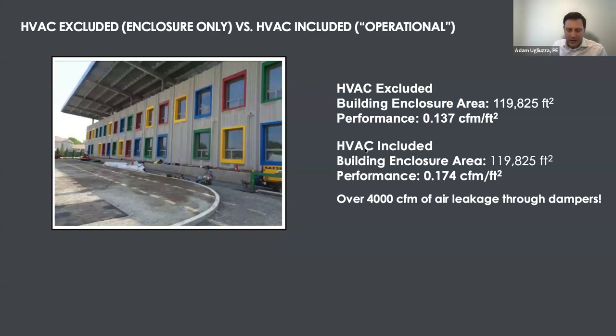Here's an example of, as I mentioned before, dampers leak. So if you're worried about passing this test, you do not want the dampers included, because it could shift the performance substantially. In this case, we tested with the HVAC dampers sealed and excluded, and then again with them included, and there was a 4,000 CFM difference. And this wasn't that big of a building either. It's 120,000 square feet of enclosure, which is roughly a 50,000 square foot building of actual floor area, not enclosure surface area. Not a big building, but you could see they did really well here. It didn't impact whether they were going to pass or fail, but if that was closer to the leakage criteria, a 4,000 CFM swing could get you past or over the allowable leakage rate.